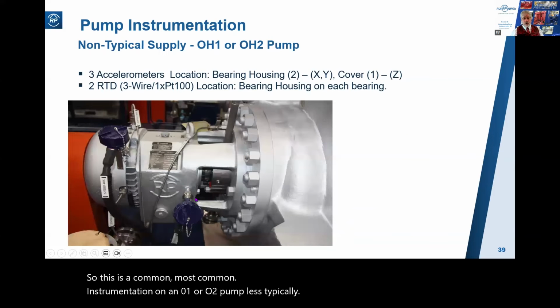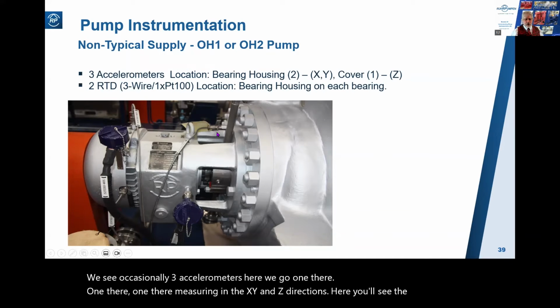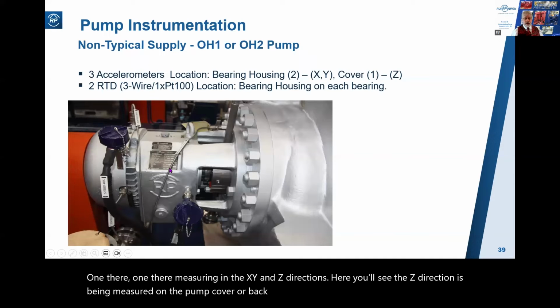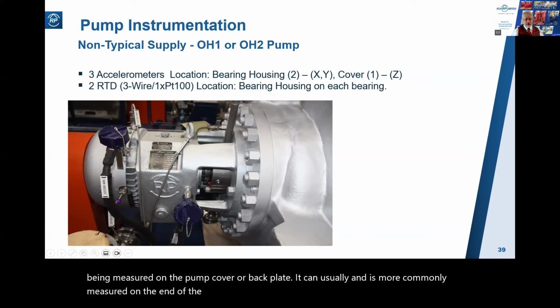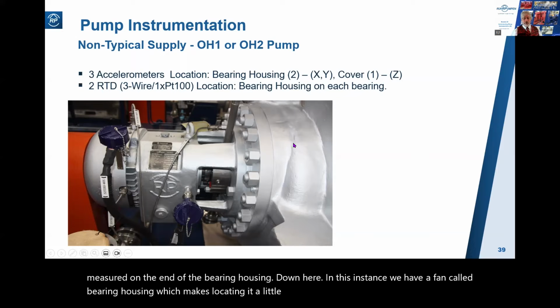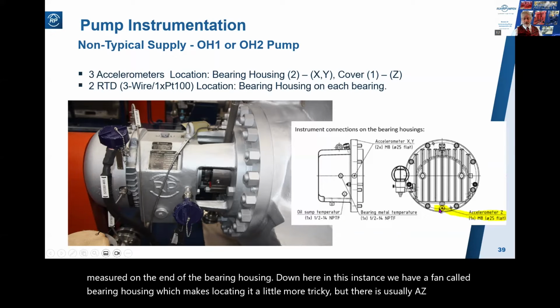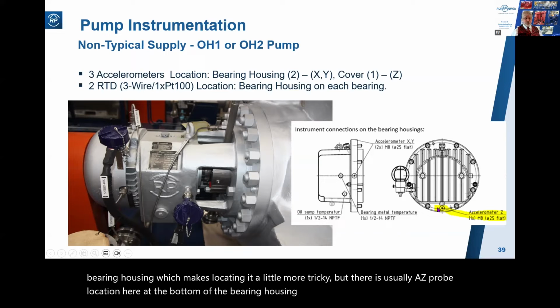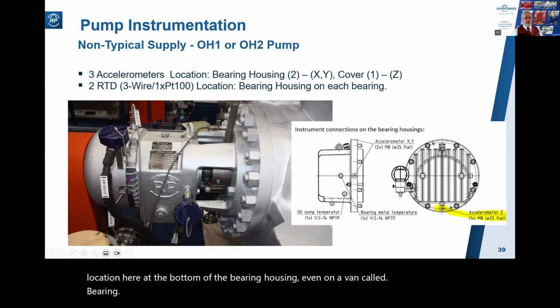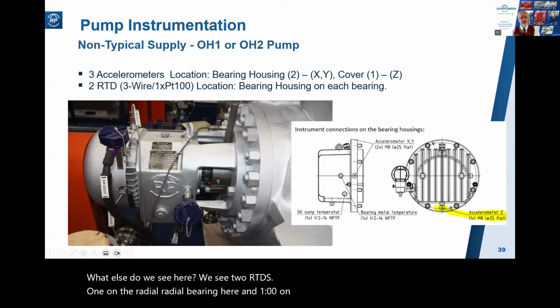Less typically, we see occasionally 3 accelerometers. Here we go, one there, one there, one there, measuring in the X, Y, and Z directions. Here you'll see the Z direction is being measured on the pump cover or back plate. It can usually, and is more commonly, measured on the end of the bearing housing down here. In this instance, we have a fan-cooled bearing housing, which makes locating it a little more tricky. But there is usually a Z probe location here at the bottom of the bearing housing, even on a fan-cooled bearing. What else do we see here? We see 2 RTDs, one on the radial bearing here, and one on the thrust bearing here.